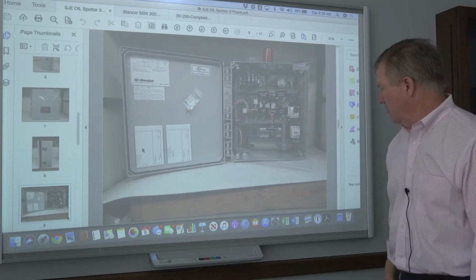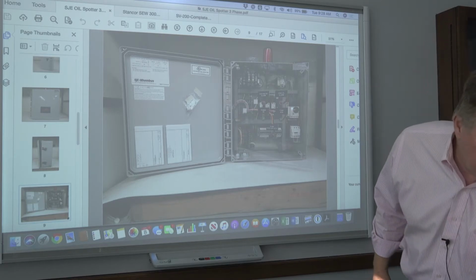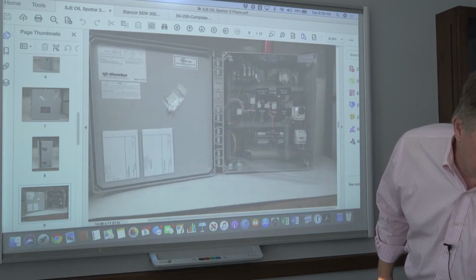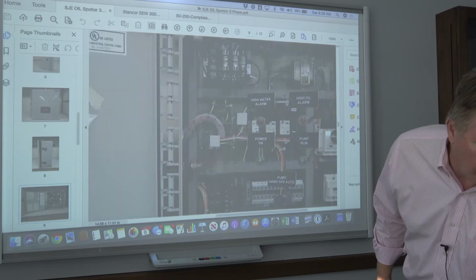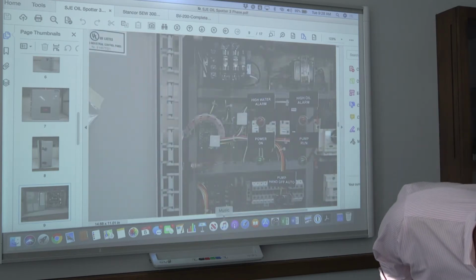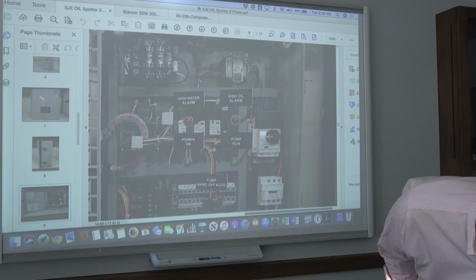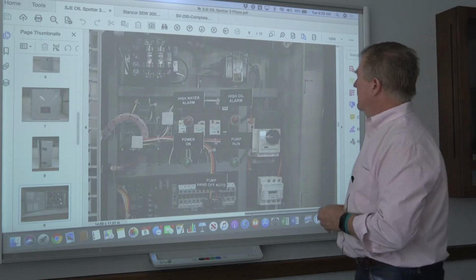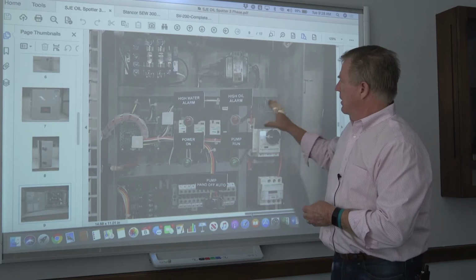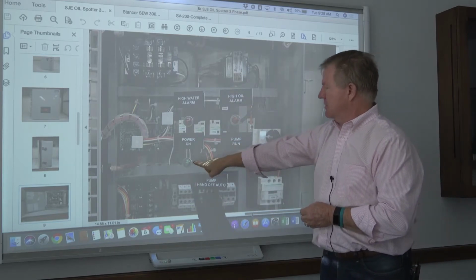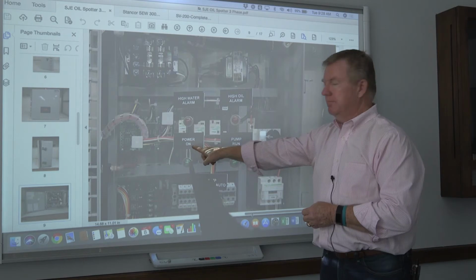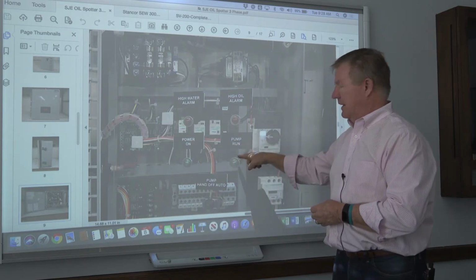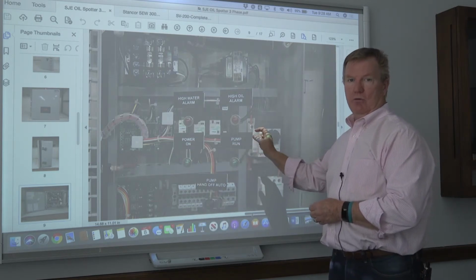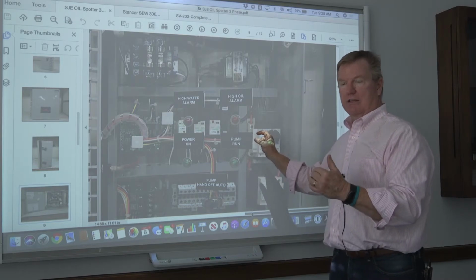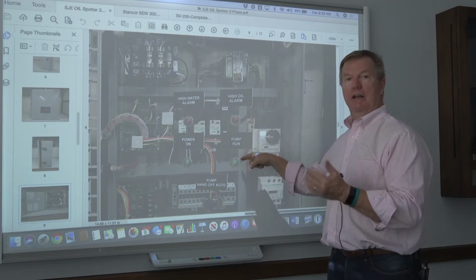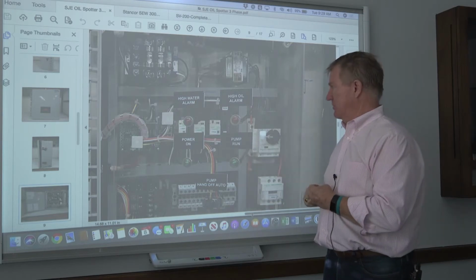Inside the controller you're going to see this is a simplex controller, so that means there is one pump. Let me slide this over so we can see. All right. There are four major outputs. There's a green light for the power on. There's a green light that will light up when the pump is running. So if the water level gets to the height that turns on the pump, this light will turn on, and then it'll turn off once that pump has turned off.